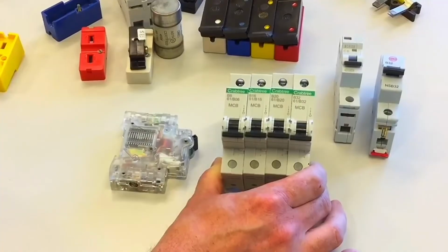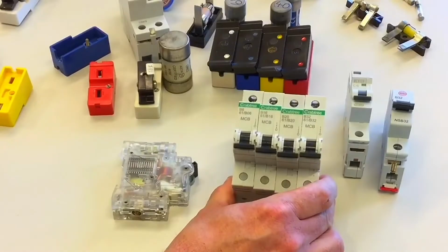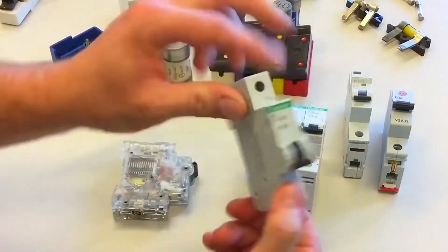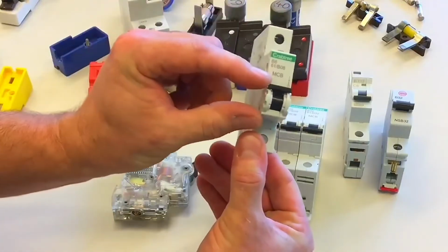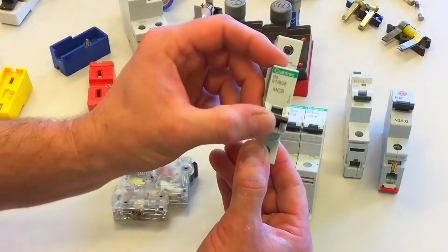Circuit breakers also have a fusing factor of 1.5 or less. Manufacturers will tell you exactly the fusing factor for those, so a more precise device than a rewirable fuse. Characteristics of the device have been set by the manufacturer, and we cannot tamper with these in any way. So in other words, it's a sealed unit, meaning that once it's operated, the device will go into the off position. Fine, the fault has been cleared. We should be able to reset that.